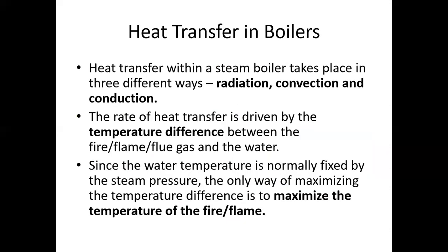We also need to consider the heat transfer involved in a boiler. Heat transfer within a steam boiler takes place in three different ways: radiation, convection, and conduction. The rate of heat transfer is driven by the temperature difference between the fire, the flame, and the water. The higher the temperature difference, the higher the heat transfer. Since the water temperature is normally fixed by the steam pressure, the only way to maximize the temperature difference is to maximize the temperature of the flame.